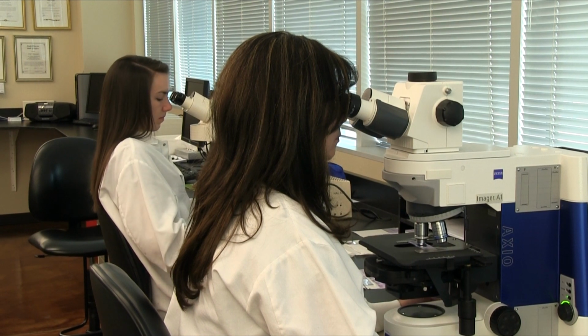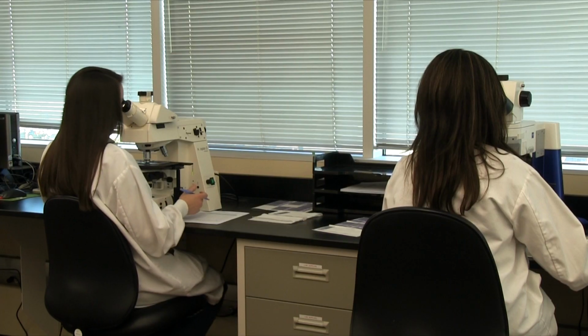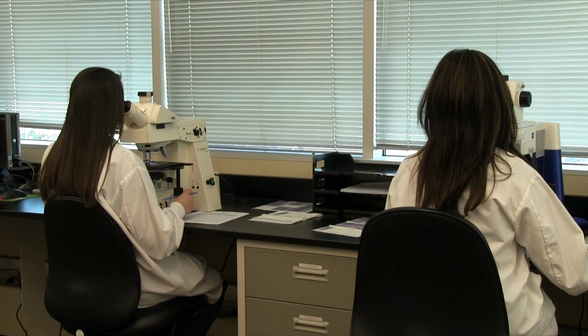The landscape of biocompatibility has been very dynamic recently, specifically in ISO 10993-3 and 10993-4, genotoxicity and hemocompatibility. With genotoxicity, the standard states presently that you need to perform 3 tests: the Ames test, the mouse lymphoma test, and then the chromosome aberration test.